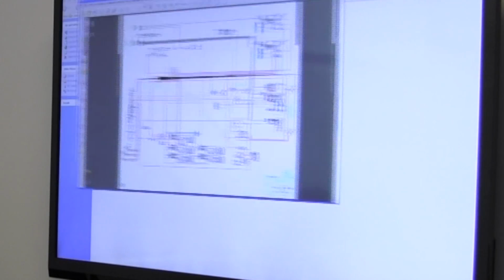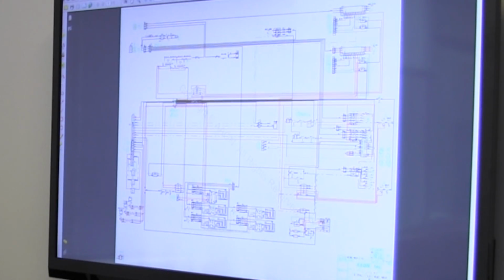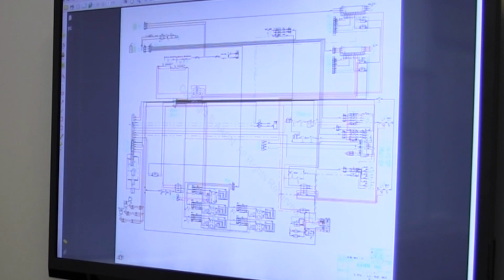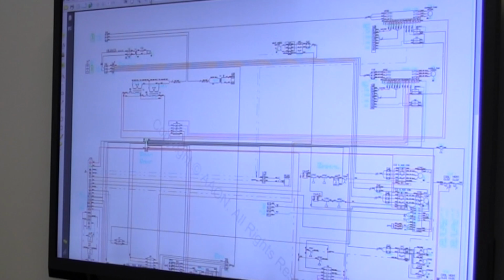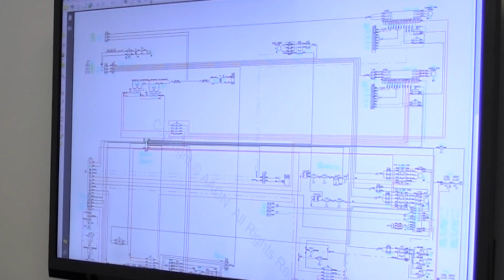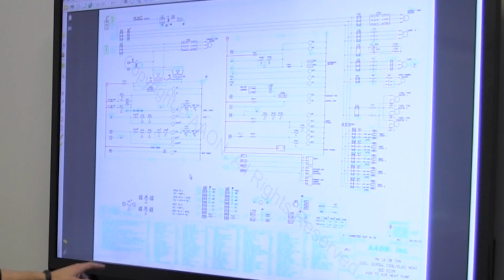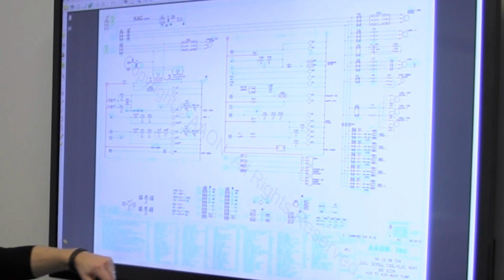And the wiring diagram is laminated on each unit on the control access door. They're all color-coded, and the wires match the color coding, so it really helps in troubleshooting. They're laminated, so hopefully they'll be with you for the life of the unit. Are they labeled also? Yeah, for the most part, every single component has a label somewhere near that component, whether it's a sensor or whatever. And then there's acronyms galore, and the legend is in the ladder diagram. So down here, every acronym that's used is defined.